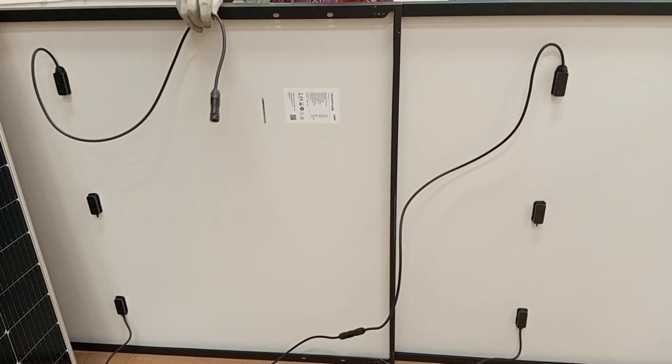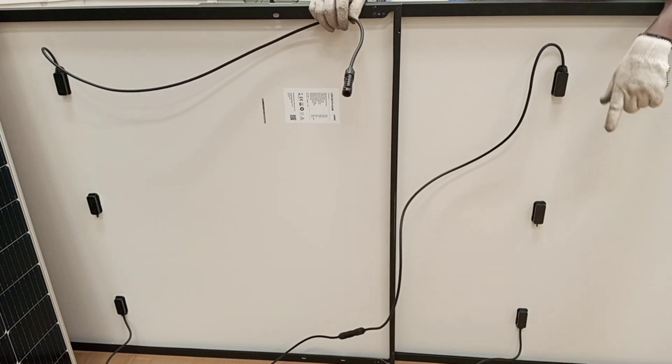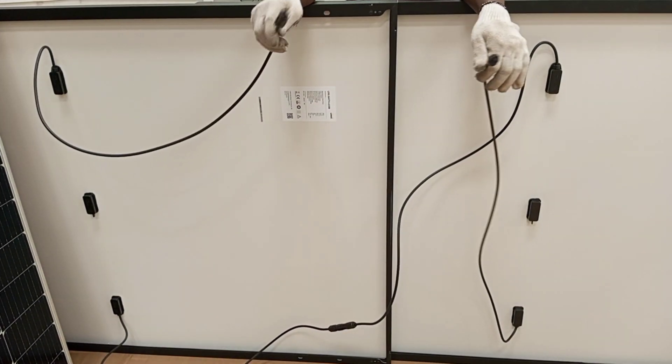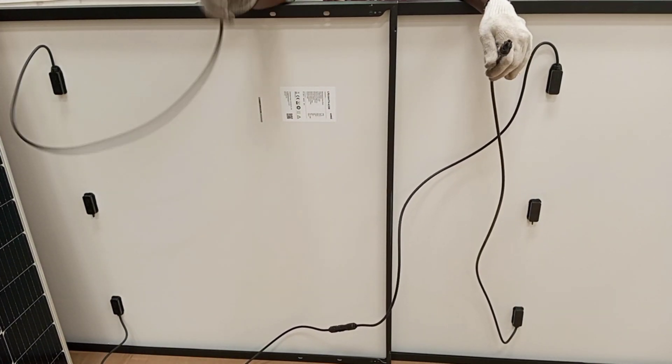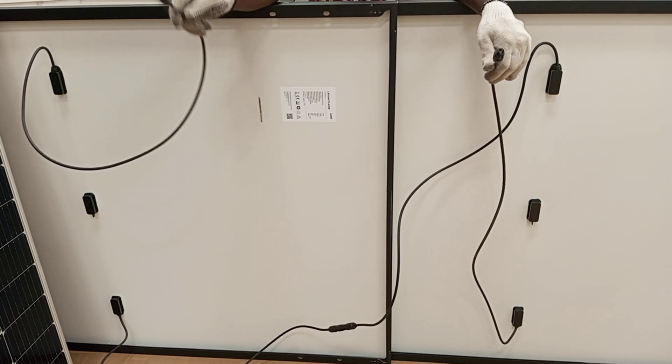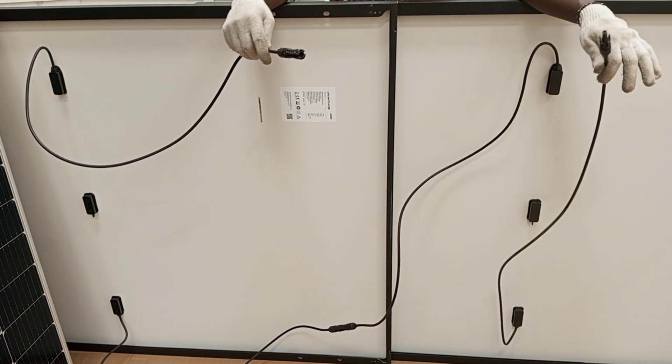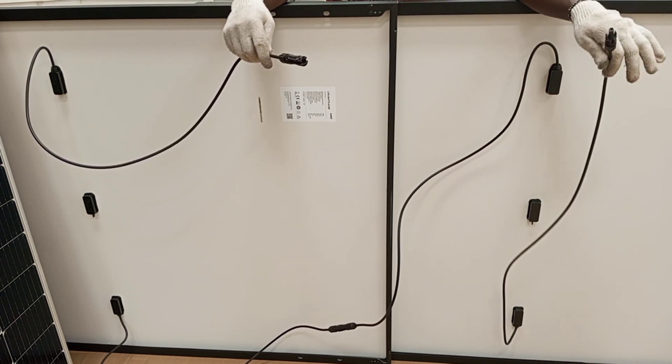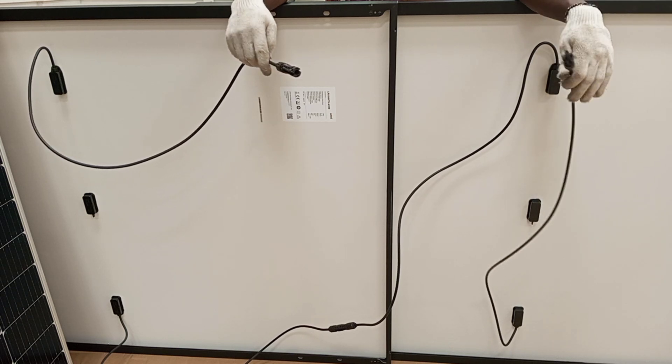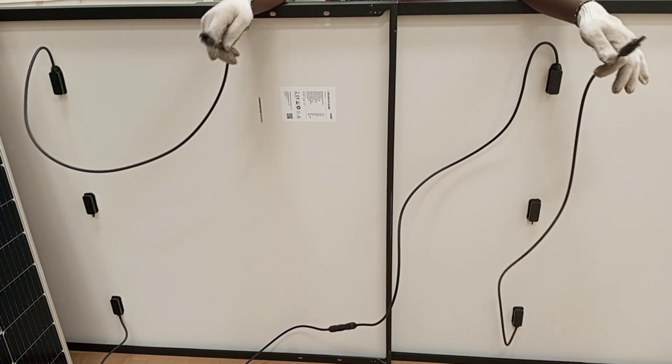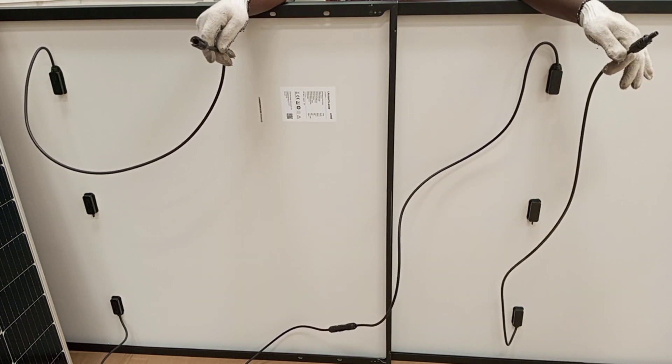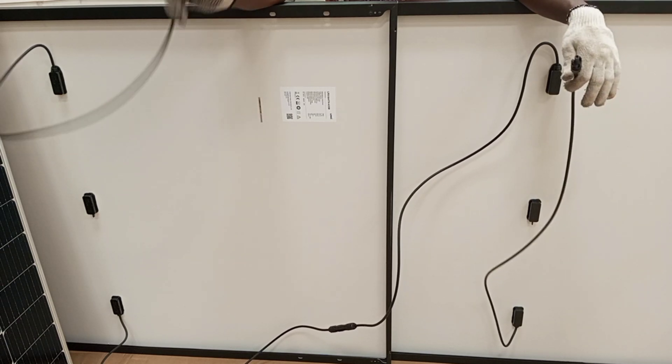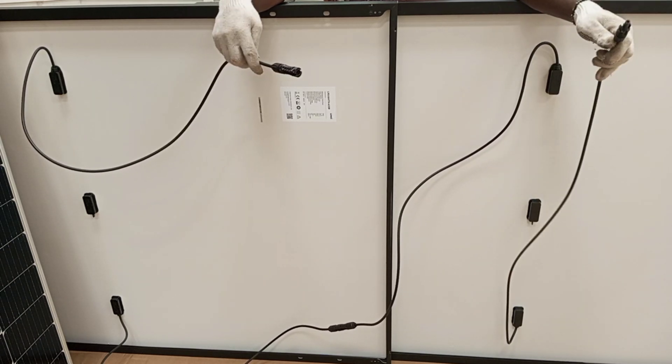So after the connection you have one negative output here and then one positive output here. At the end of our series connection we have one negative cable from the first panel and one positive cable from the last panel. In actual fact, we could connect a lot more panels in series, and at the end of the connection we have one negative and one positive output to either the charge controller or the inverter.